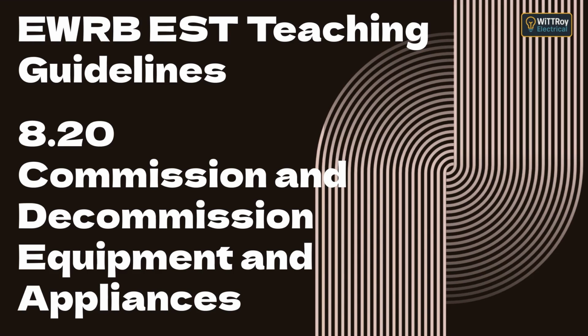Summary. To wrap up, always isolate and lock out before disconnecting. Label all conductors as you remove them. Handle each cable type according to its material. Maintain correct polarity and verify before energizing. Understand the dangers of interchanging conductors. That concludes Topic 8.20, Commission and Decommission Equipment and Appliances.